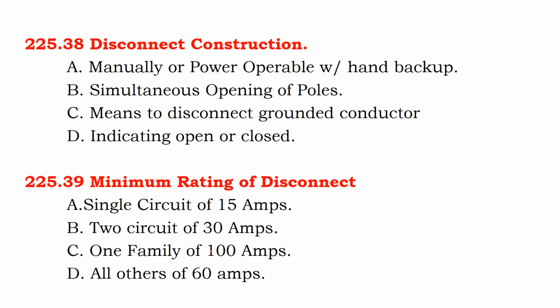So what constitutes a disconnect switch? Mainly, the thing to know is that if they're power operable, they also need to be operated manually in order to qualify as that main disconnect switch. A main disconnect switch needs to be field operable by an on-site person. Just having it automatically open on a control circuit does not constitute your main disconnect.